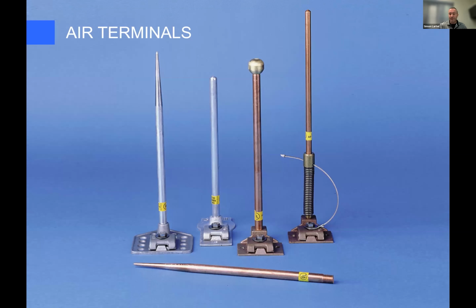I've seen a galvanized steel roof rust through in about 10 years, and that's through. You can see into the building underneath it. That's because somebody put lightning protection on the roof. It wasn't aluminum, it was copper. The copper caused corrosion, and the roof wasn't very high quality to begin with, but it did rust through in a matter of about a decade. So we want to make sure we are using the correct materials.